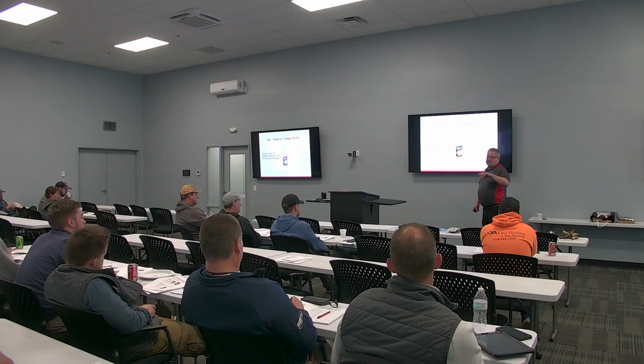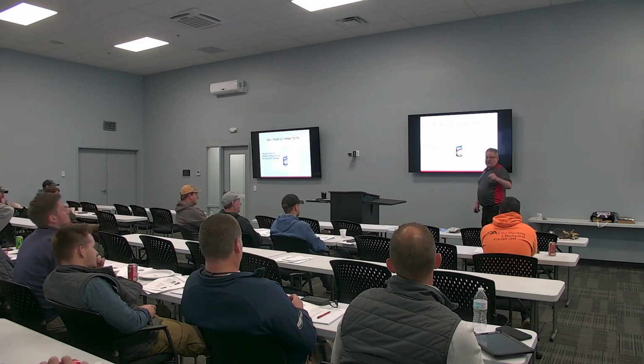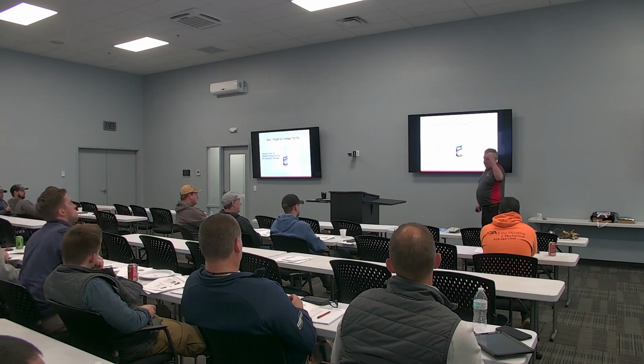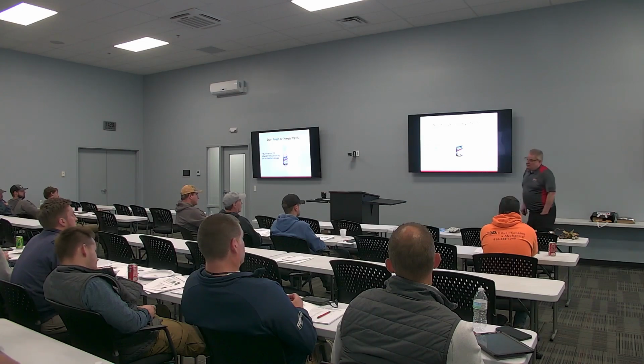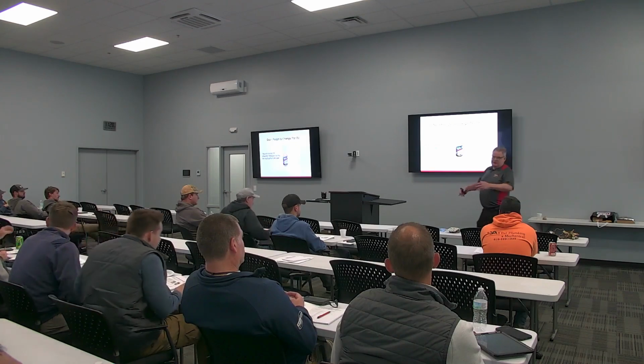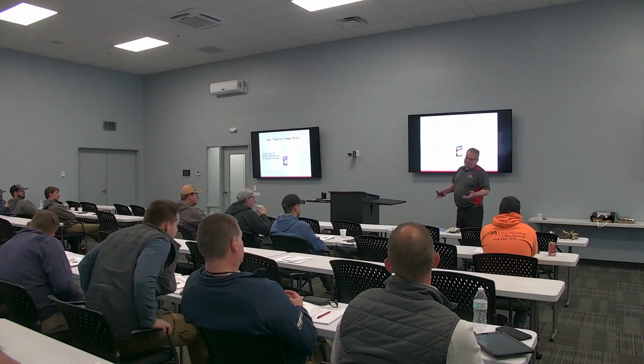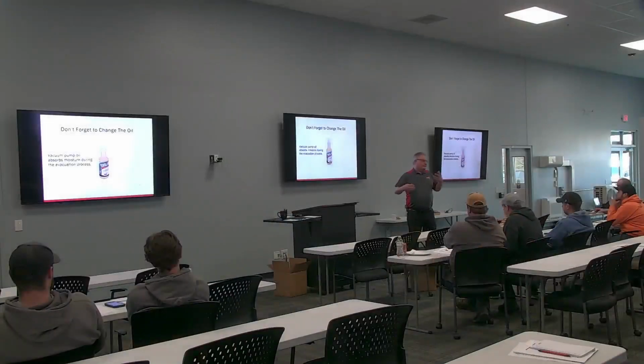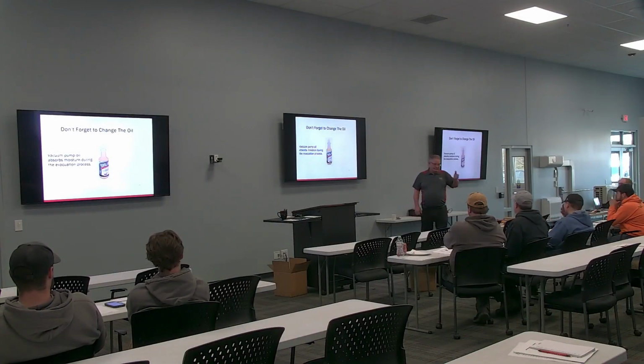If you question how much dry oil improves your pump, take your vacuum pump when you have not changed your oil, put your micron gauge directly on it, turn it on. Change the oil, try it again. Huge difference. Huge difference. So change the vacuum pump oil. It should be every time you use it, or obviously, if you're doing Mrs. Smith's little 2-ton and she's got a 15-foot line set and I just changed the oil and I'm going to do another one this afternoon, well, I probably don't need to change that. But if you're doing big systems, dirty systems, wet systems, change the oil.